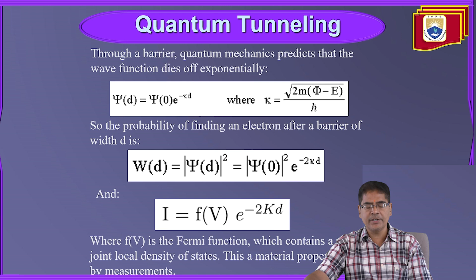the local density of states. This is a material property which is obtained by measurement. So the quantum tunneling current is given by I proportional to e power minus 2kd, where k is approximately the square root of 2m phi by h. Plugging in typical values for mass and phi, where phi is the average work function of the tip and the sample, when the distance changes by 1 angstrom, the current changes by a factor of about 10.